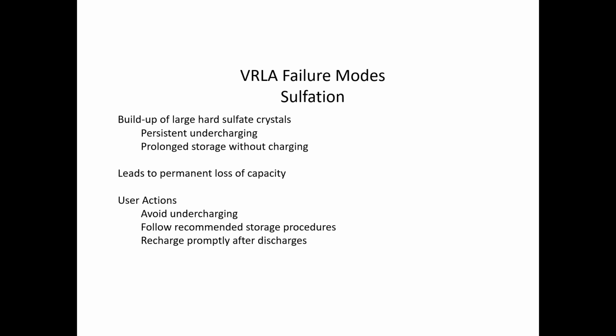So failure modes, what happens? Sulfation can happen on the positives. There's a couple items that can happen on that. Consistent undercharging. It's not uncommon for us to come across a battery where we'll see a manufacture date of, say, 2017, but an installation date of 2019, like it was just installed this past year, and the battery was stored for a year and a half, which in and of itself is not necessarily bad as long as they periodically charge that battery while in storage.